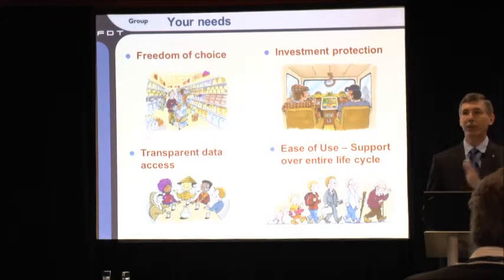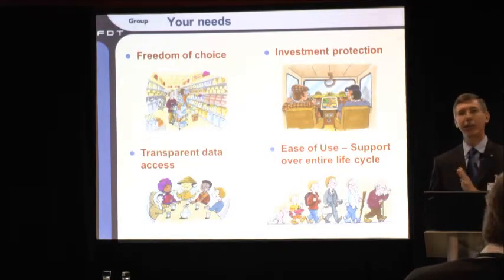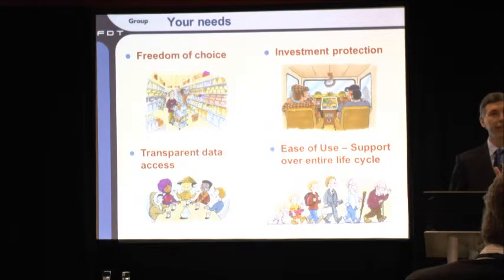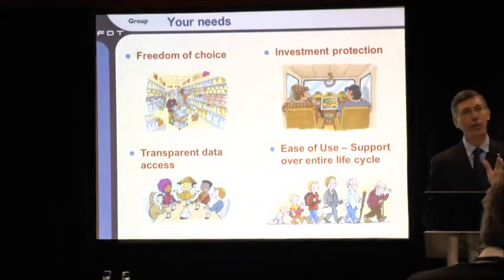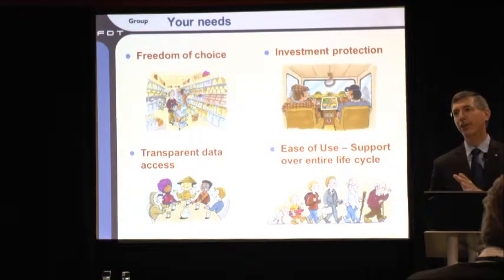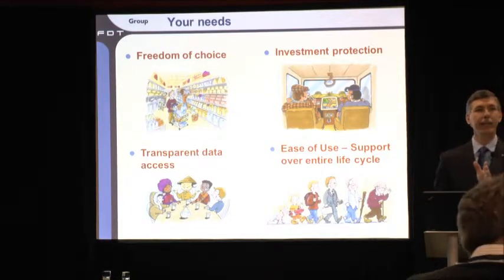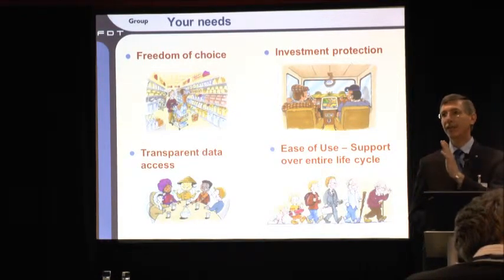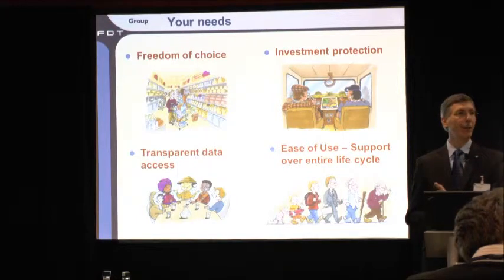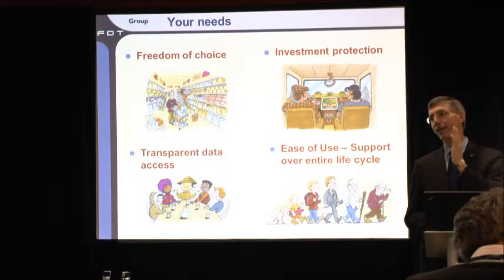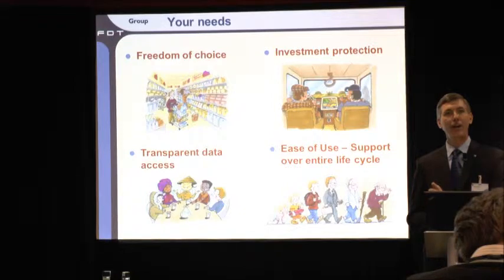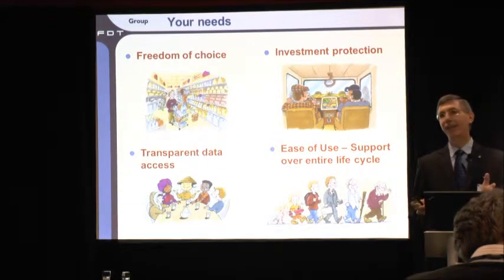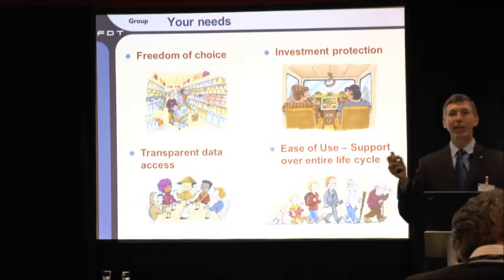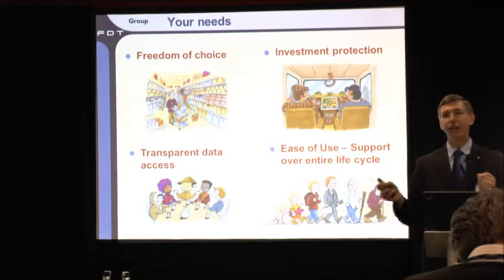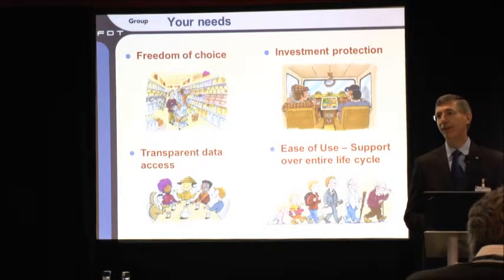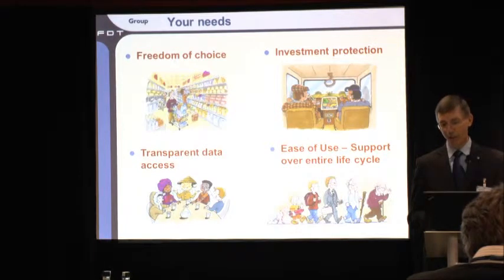But that carries throughout the entire life cycle. During the commissioning of the plant, as we'll show in some of the user stories, they saw significant reduction in commissioning time because they were able to pre-configure, so that when it came time to turn on the devices, if they weren't at the right spot on the network or didn't respond, you immediately know something's wrong. You don't wire up the entire plant and then spend weeks ringing out end to end just to make sure you've got all the I/O points right throughout the plant. The FDT standard helps you with that.